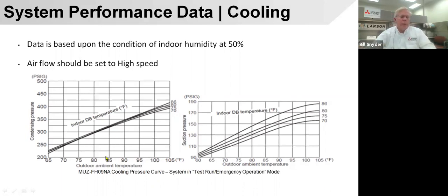That fixes the compressor speed at one particular speed. And in this case, this is your condensing pressures at the given outdoor temperature. And this is your suction pressure at a given outdoor temperature. So if it's 80 degrees and you're reading 130 pounds of suction and it's 75 degrees inside, it's performing just fine. This is, again, not intended for charging. It's just to see that the system is operating properly. If it isn't operating properly, make sure the coil is clean. If you think you have a leak, look for the leaks. If you do have a leak, remove the refrigerant and recharge by weighing in the charge.